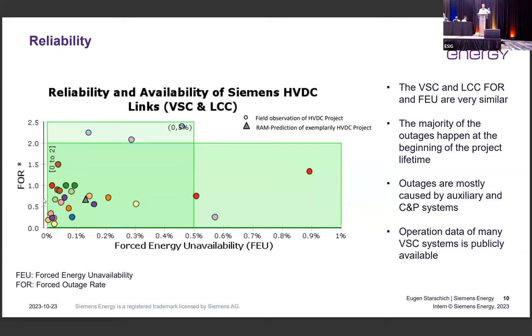When we started, we had a statistic for the VSC and for the LCC technology separately. At some point, we realized it doesn't make any sense because the rates are very, very similar. The reason is that the majority of the failures are not due to very specific VSC or LCC parts, like the converter itself. Most failures come from auxiliary systems, control and protection systems, which are very similar. So the difference is actually not that big.